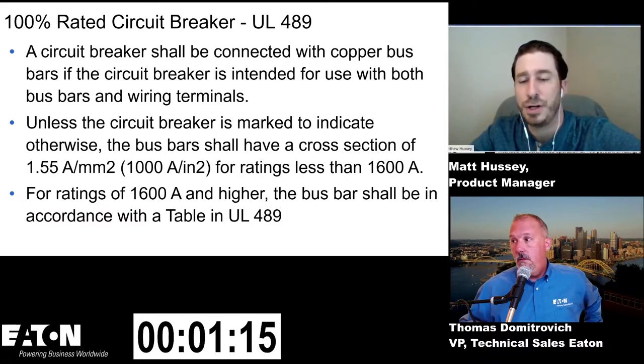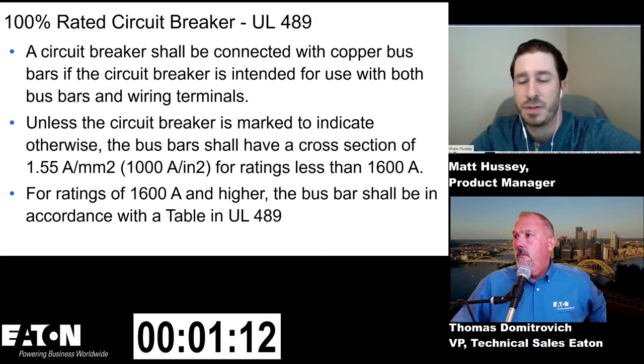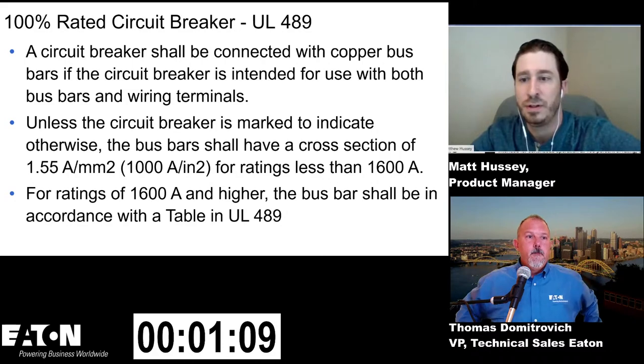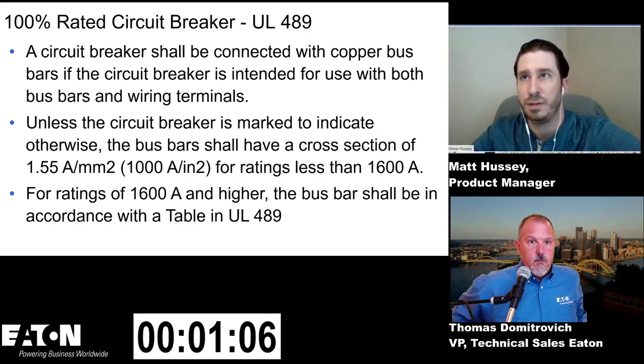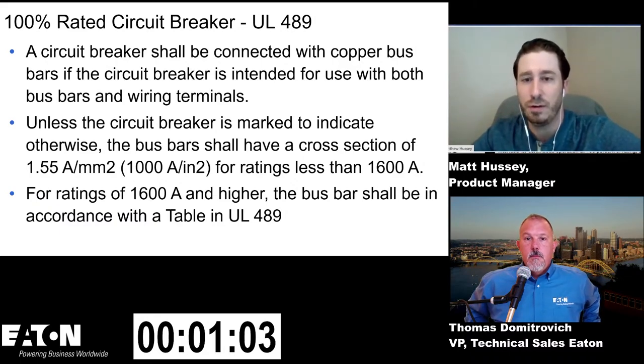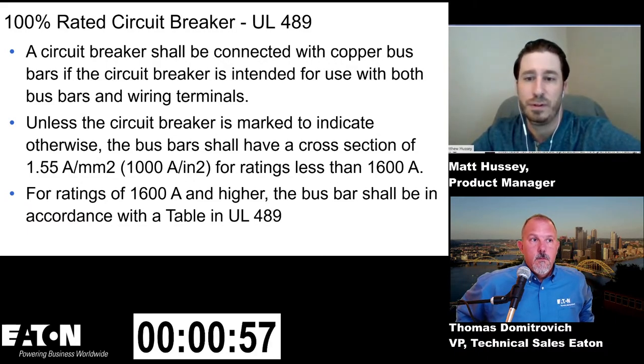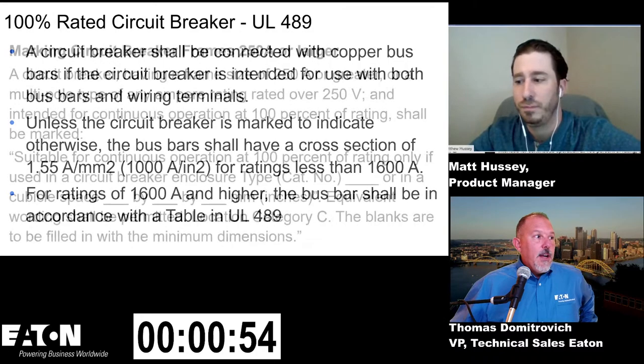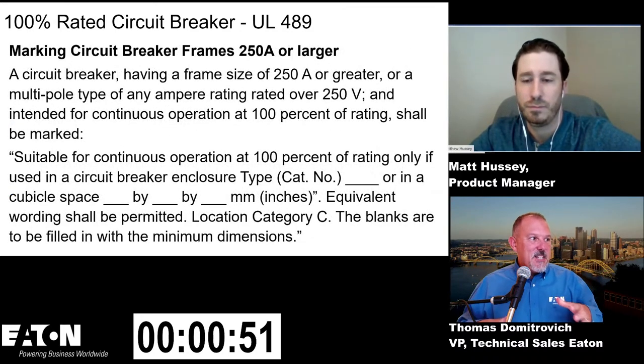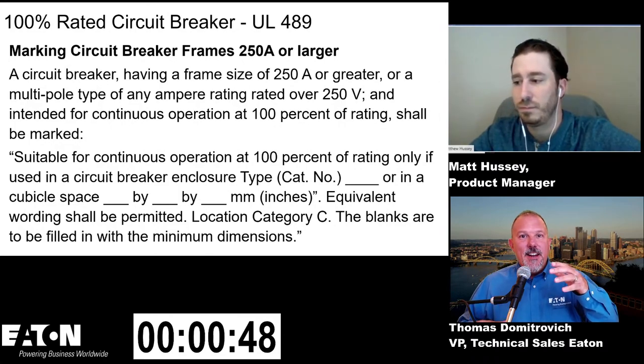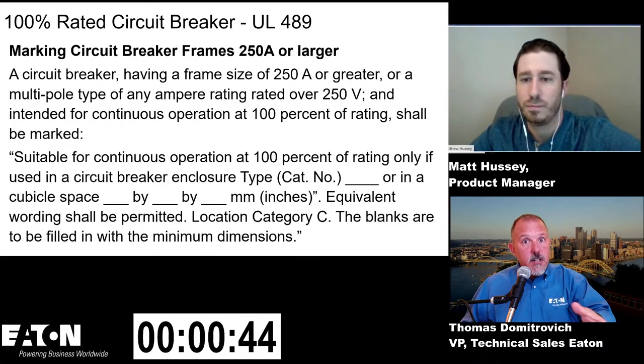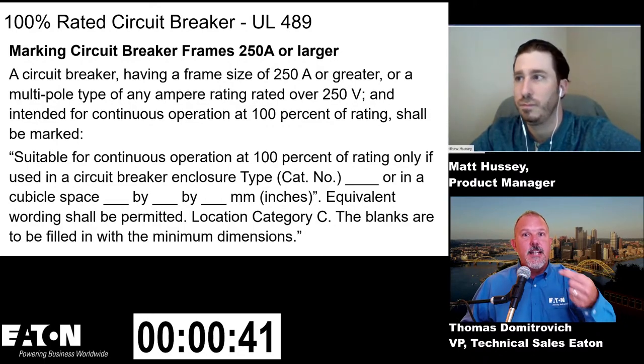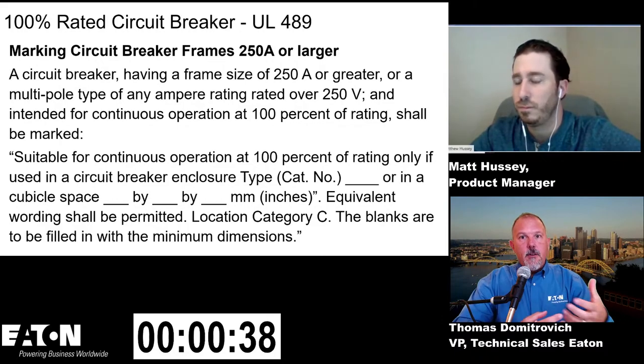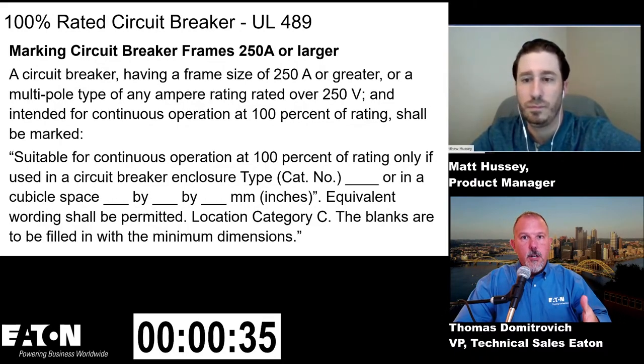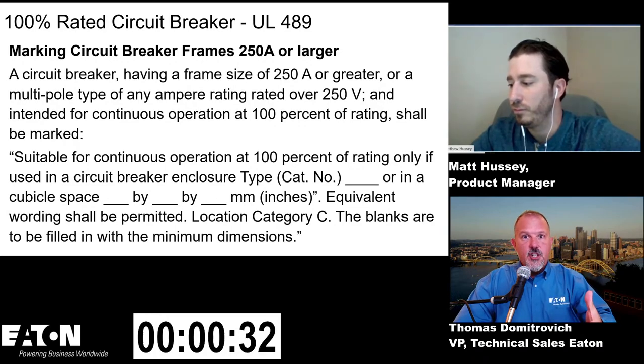Yeah, and what they're trying to describe there is ensuring that a certain amount of cross-sectional area is present, to balance out the equation of a certain amount of copper to handle the amount of temperature buildup. Right. And so this is what gets into the mix, because now we're starting to understand that it's not just the circuit breaker that's got to be labeled 100% rating. I'm using that circuit breaker together with the enclosure of the assembly, whether it be a panel board or whatnot. I have to make sure that they both work together.